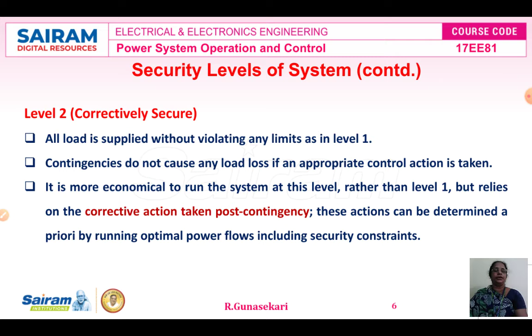So it is more economical to run the system at this level rather than level 1, that is the secure level, but it relies on the corrective action taken post contingency. These actions can be determined a priori by running optimal power flows, including security constraints. This is level 2.